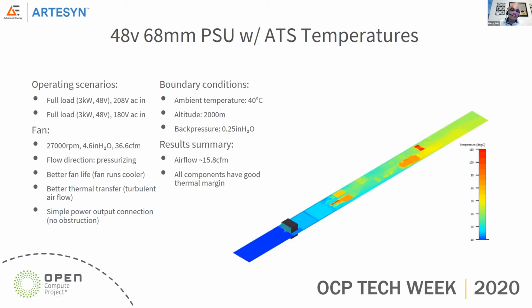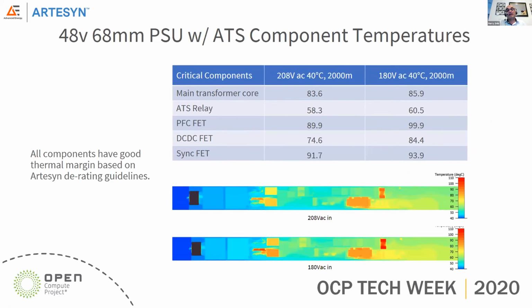In the next slide we deep dive into the key parameters everybody is concerned about: what margin do I have on my main transformer, the ATS relays, my power factor FETs, DC to DC FETs, and the sync FETs. At 208 volts, at highest temperature and highest altitude, the temperatures are well within the derating guidelines, which are not only Artesyn guidelines but also IPC guidelines. You will see, however, in the bottom simulation, the 180 volts runs a little bit hotter, but that's expected as the peak currents are almost always higher at low line input. That's the flow therm simulation.